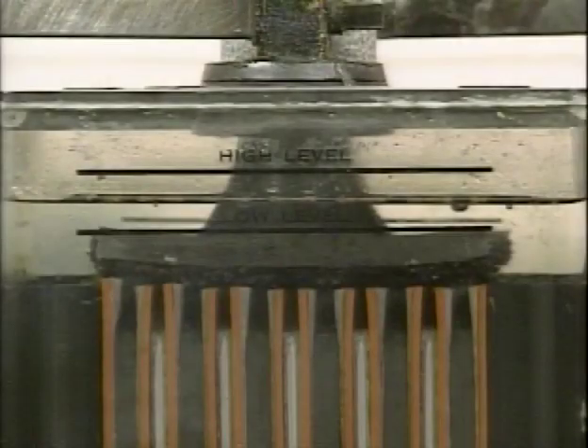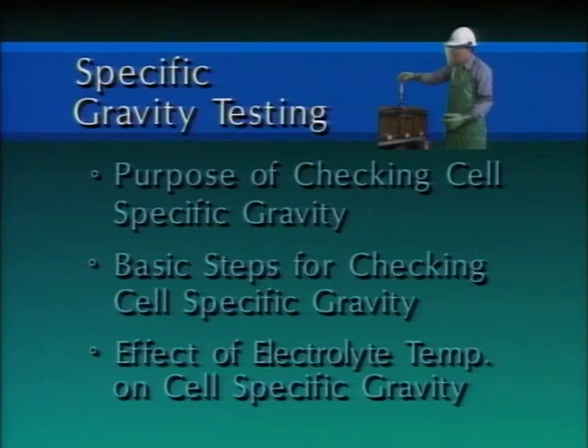The term specific gravity for a substation battery cell refers to the density of the electrolyte in the cell in relation to the density of water. A cell's specific gravity is normally an indication of its state of charge. This part of the program will look at specific gravity testing of substation battery cells. The key points that will be addressed include the purpose of checking cell-specific gravity, the basic steps for checking cell-specific gravity, and the effect of electrolyte temperature on the specific gravity of a cell.